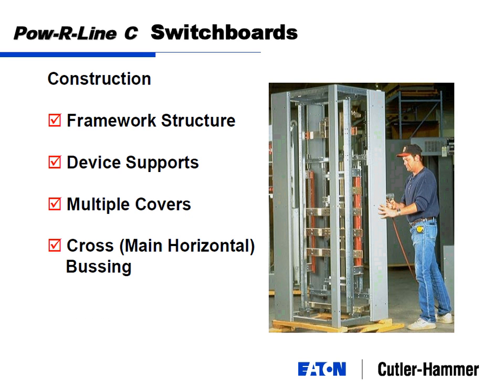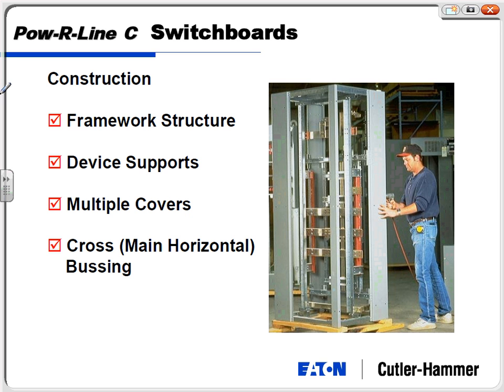Switchboards really consist then of a framework structure, 4 posts, framework all the way around the top and the bottom. You can see right here, here, and here, horizontal bus. Okay, so that's your A, B, and C phase. And what that gives you is the ability to stack multiple structures side by side. So you can put in one main device, put some feeders on the same type of panel board. You'll have a vertical busing in there. Main device with some feeders, and just keep adding sections and sections and sections until you get everything put together.